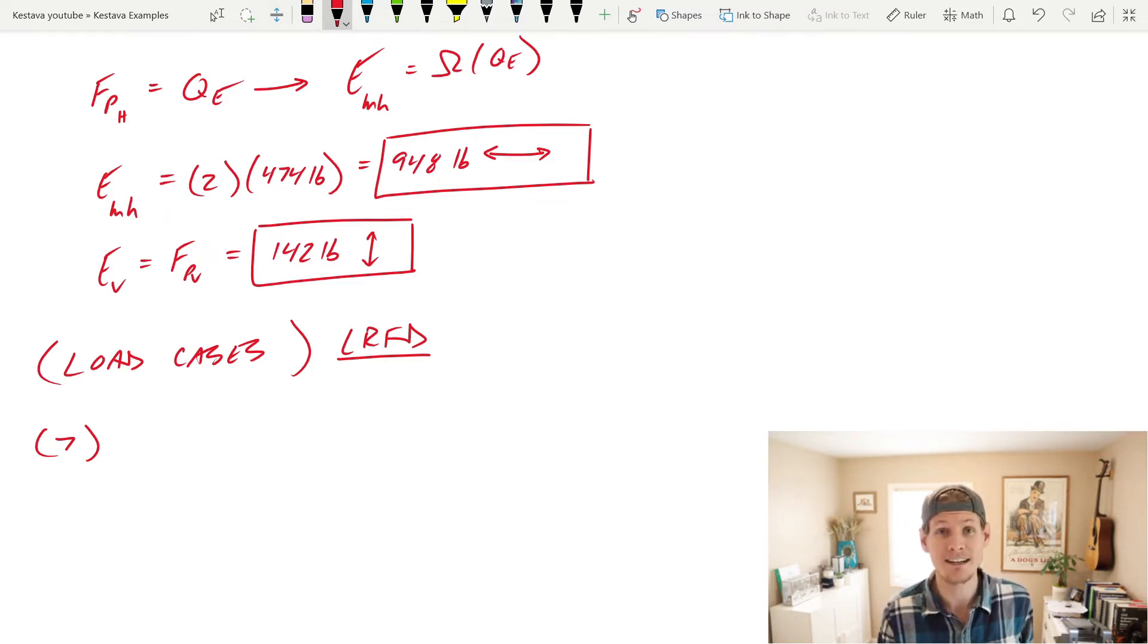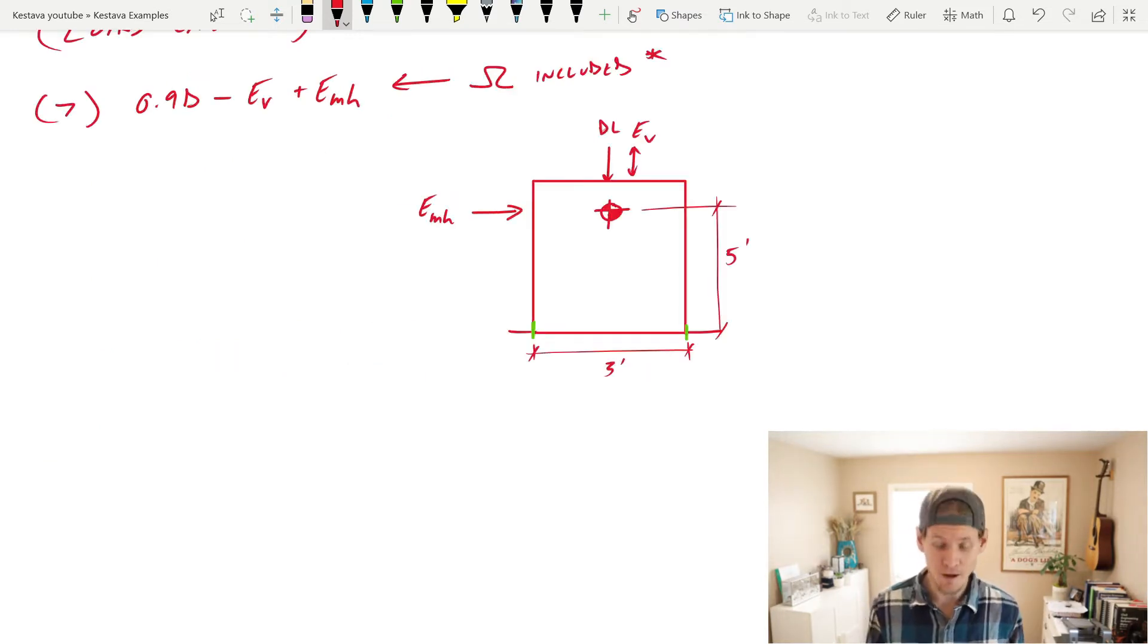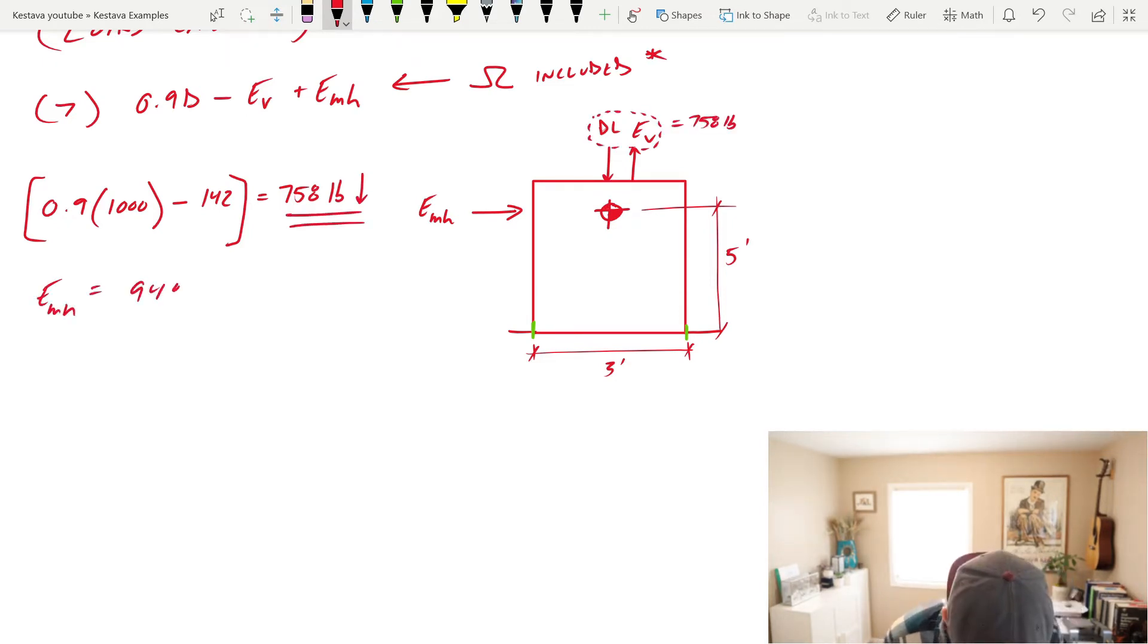So that would then result in the highest tensile force that is acting on an anchor. And you'll see why here. And here's our diagram all set up with our loads relatively applied to it. We just need to apply the actual values to them. 0.9, we know our dead load is 1,000 pounds. That's the weight of our unit. But we need to subtract out E sub V from that. So in this case, we can delete that and actually just have it pointing upward because we're subtracting. So we're saying that the vertical component of the seismic demand is actually lifting that unit up, which is making it lighter, which is making the condition worse for overturning. EV is 142 pounds. It's going to equal a net dead load of 758 pounds downward. And then EMH is 948 pounds.